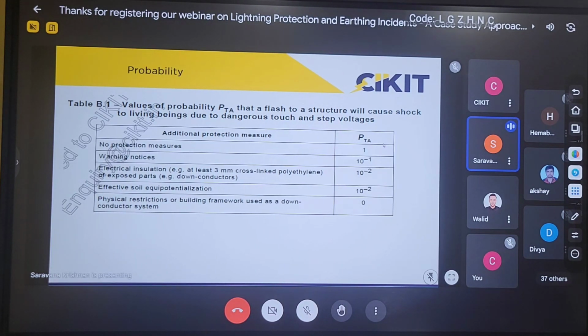The first one is the probability value due to shock to living beings from dangerous step and touch voltages. For these two sources, lightning striking the structure and lightning striking the power line, the two important parameters to be considered are the step and touch voltages due to this high impulse current. For a substation, we can do a proper calculation. We know what the fault current will be, and we provide the earth mat for reducing this risk. But with lightning, we don't have much idea about the magnitude or how to do the calculations. And here the current duration is also very short, so a tedious calculation would be very difficult.